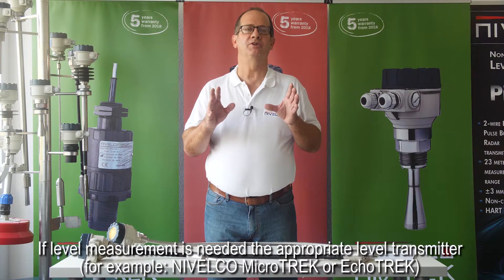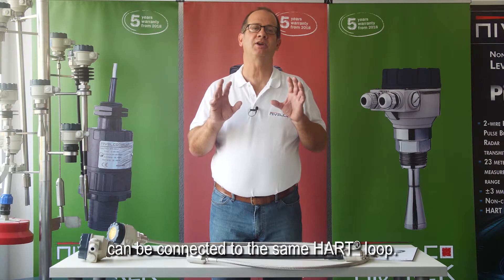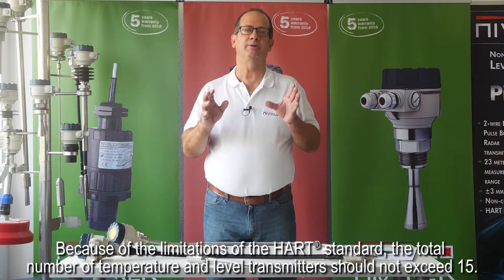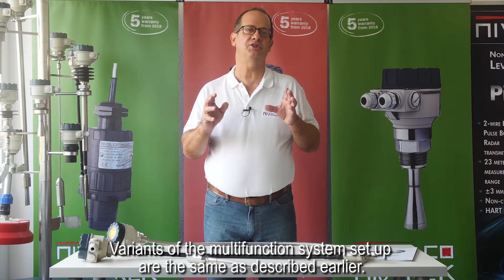If level measurement is needed, the appropriate level transmitter — for example, Nivelco MicroTREK or EchoTREK — can be connected to the same HART loop. Due to the limitations of the HART standard, the total number of temperature and level transmitters should not exceed 15. Variants of the multi-function system setup are the same as described earlier.